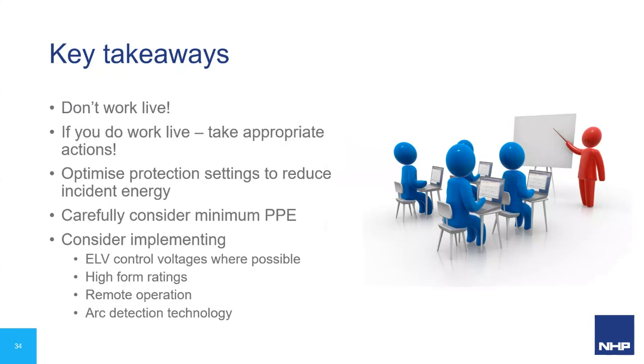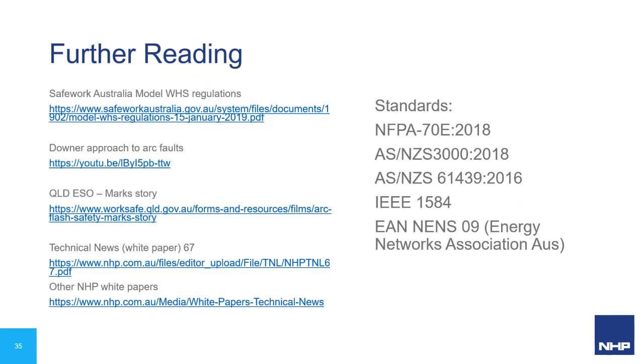So a few of the key takeaways. Number one, don't work live, or if you do, take appropriate actions. Optimize your protection settings to reduce incident energy. Carefully consider the minimum PPE required for the job, and consider implementing ELV control voltages, high form ratings, remote operation, arc detection technology. So there's actually quite a bit there that you can start considering. I have listed some further reading here, which will be available in the follow-up emails that go out. One in particular is the Technical News, an article that I wrote in essay form covering similar information.